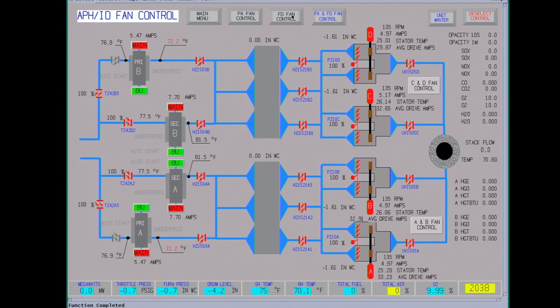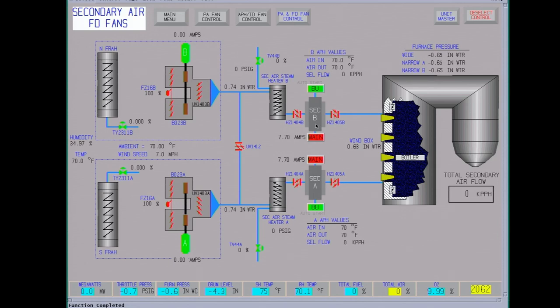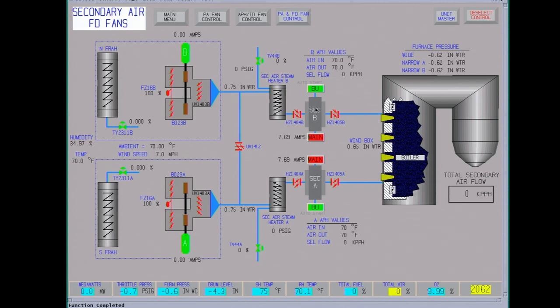So we're going to go to the FD fan screen. These have air heaters on the intake into the fan room. You want to prevent the air cooling off the plates below about 140 degrees on your air heaters, otherwise you condense moisture. And that could have some corrosive substances in the moisture. It'll corrode your air heaters. So we preheat the air to minimize your average cold end air temperature. Basically you have your air heater coming in, this is the fan room. It's your secondary forced draft fan. That comes in through your secondary air heater. The flue gas comes the other side, opposite direction. From here it's feeding the wind box on the boiler. This feeds your burners and your over fire air.